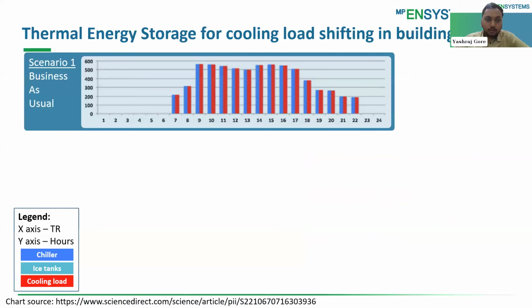So here we will talk about three different scenarios in which we will utilize thermal energy storage and demonstrate how you can shift your cooling demand to off-peak hours. In the first scenario, you can see in the red line you have your cooling load, and the chiller is basically supplying the required demand, based on the cooling demand, and you are supplying it accordingly.